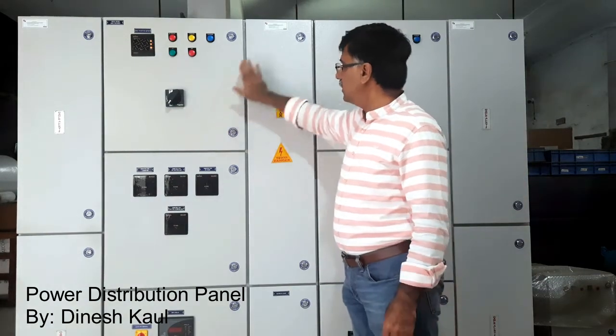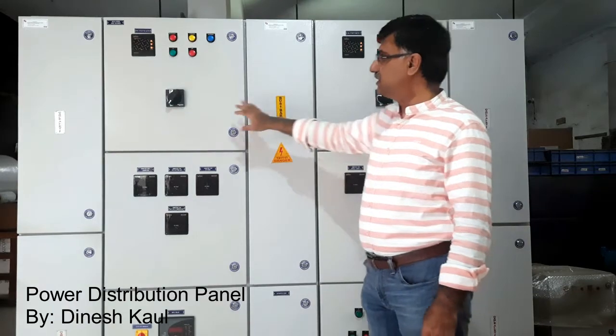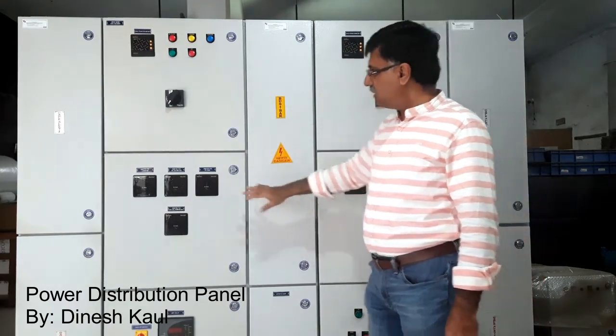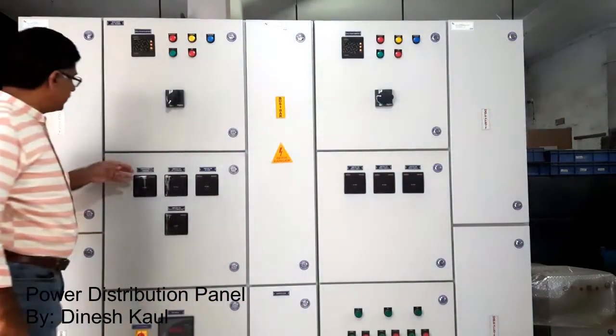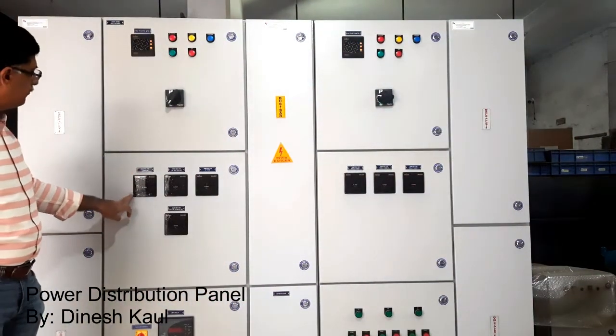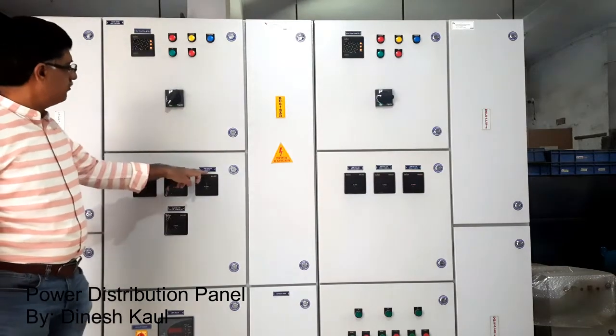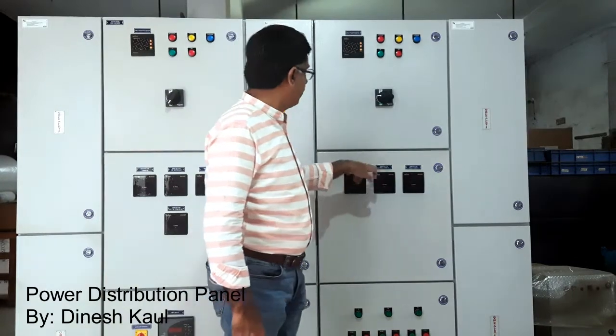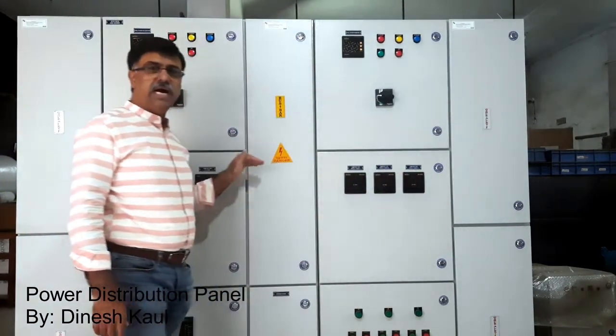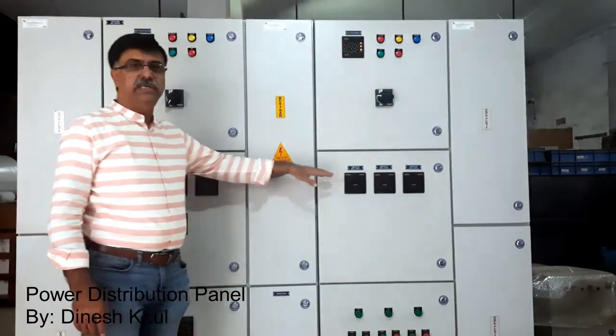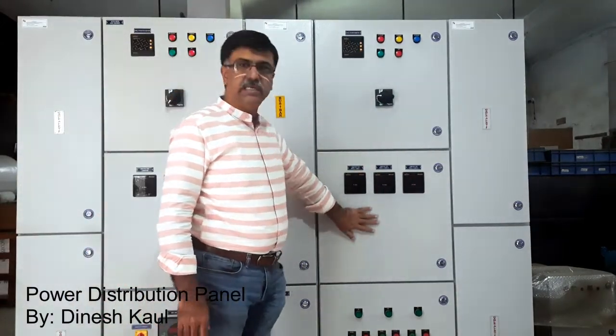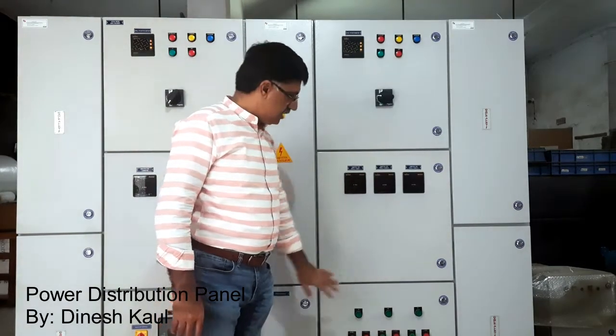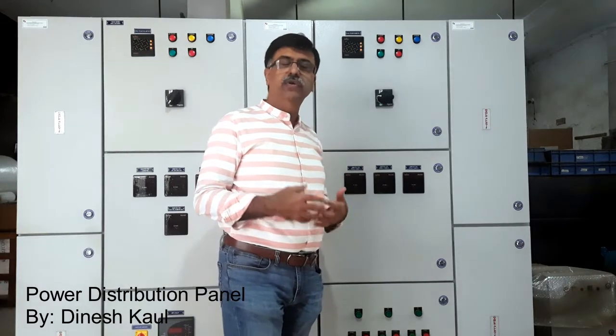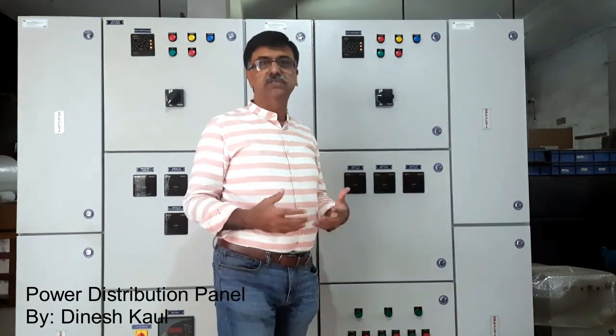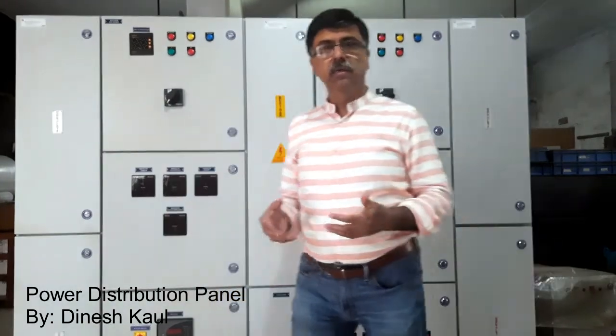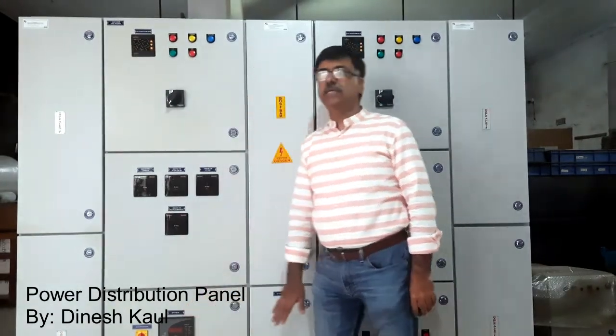So two incomers, then you have one bus bar section where both of these are terminating, and after that you have the outgoers. In this, for example, the client wants ampere, this is for a laminator, for a die cutting machine, for an air compressor, for single phasers 1, 2 and 3. Since these are the higher loads, these have inbuilt ampere meters here, and the ones that are smaller loads don't have ampere meters. Then for power correction, we need to have capacitors which switch on and switch off automatically. So then you have an automatic power factor correction relay.